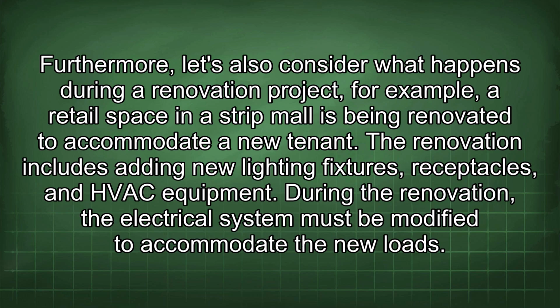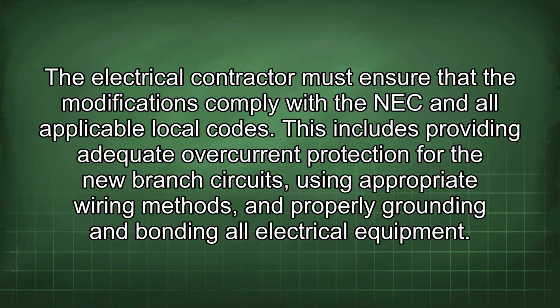Furthermore, let's also consider what happens during a renovation project. For example, a retail space in a strip mall is being renovated to accommodate a new tenant. The renovation includes adding new lighting fixtures, receptacles, and HVAC equipment. During the renovation, the electrical system must be modified to accommodate the new loads. The electrical contractor must ensure that the modifications comply with the NEC and all applicable local codes.